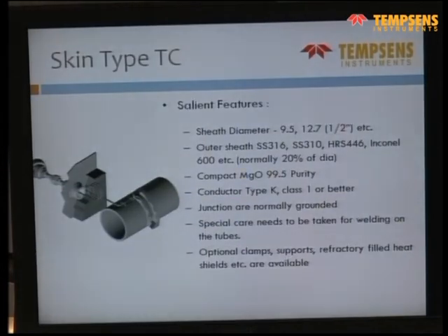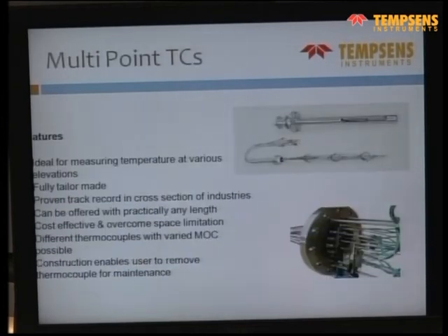Then for the oil and gas industry, skin type thermocouples are there. They are again for the tube temperature measurement. So skin type thermocouples are quite common for oil and gas, also for power plants. In case of oil and gas, because the tubes can move because of temperature, there is a spring arrangement so that the thermocouple would be intact even with the movement of the tube. These are multi-point thermocouples. As we discussed, they are similar to the ones we discussed there. So we can have multiple points going from a flange, and they can be constructed as per your requirement.